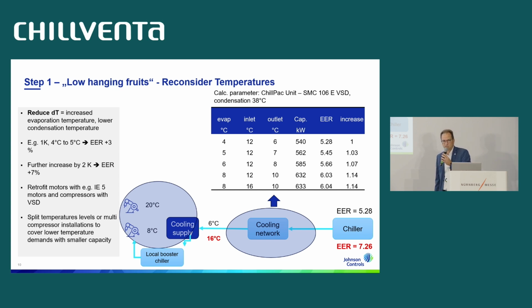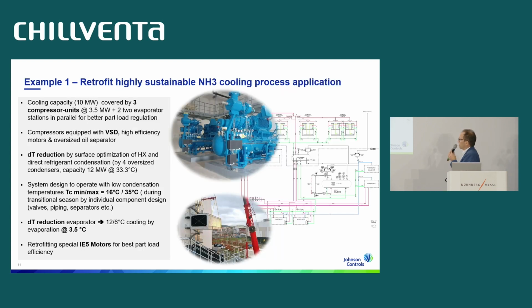And this is not theory, but I have here a practical retrofit example by our customer where the cooling demand was 10 megawatt. This was fulfilled by one system before. So what we've done here, we have done covering by 3 compressor units in parallel, serving each 3.5 megawatt at 2 evaporators in parallel for better part load regulation. Because typically you have a huge amount of part load during operation.